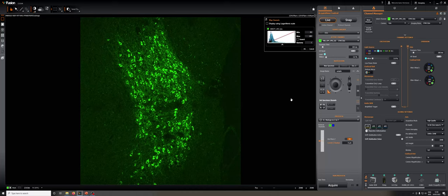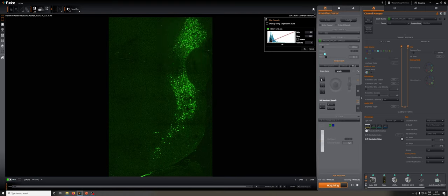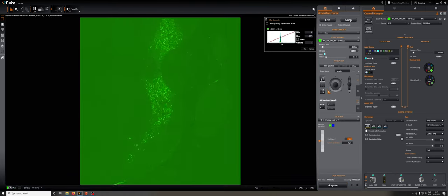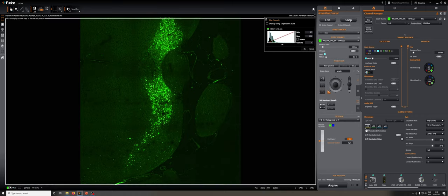Let's say we're fine with these starting settings and want to get an idea of what else is in this sample. When we click on this button, it will run a 3x3 montage very quickly and crudely, but this can be very useful for navigation. Now we have an image of a larger portion of this section. With auto contrast on, it looks more reasonable. We can use this display mode to click on a position we want to visit, and the stage will automatically go there.